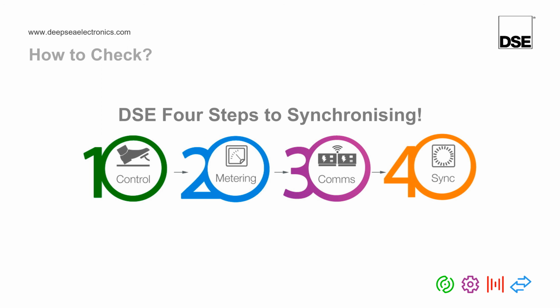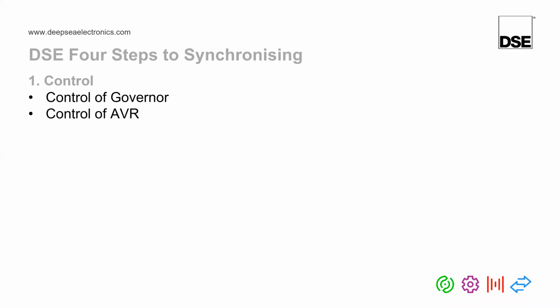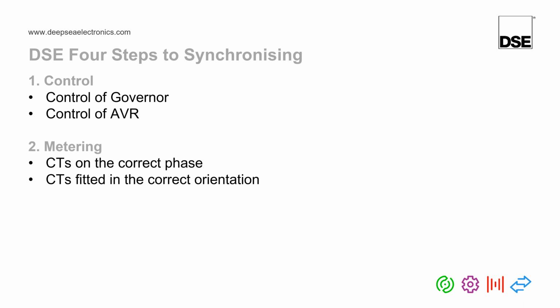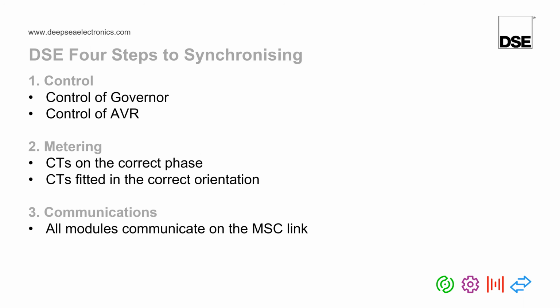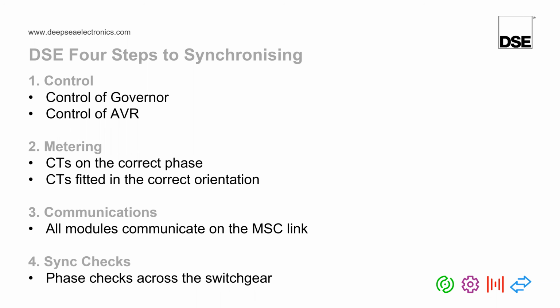And just to go over again what those DSE Four Steps to Synchronising actually are, step one is to check the control of the governor and AVR, because we need to make sure we've got good governor control and good AVR control to make sure that we have good synchronizing control and load sharing control in terms of kilowatts and kVARs, voltage and frequency. The next step is to check the metering to make sure that we can measure the current and power on the CTs correctly, because if they're incorrect, all of our power measurement will be wrong, and therefore load sharing will be wrong. We also need to make sure communications is working correctly, so make sure that MSC link is working correctly. Because if the MSC link is not working, the modules will not be able to communicate to one another. And finally, we also need to do phase checks across the switchgear to make sure nothing has gone wrong.